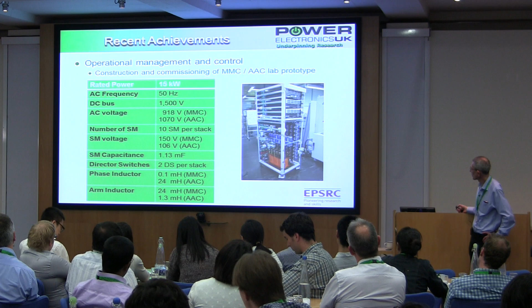What I've got here are a few slides showing the experimental system being assembled at Imperial, to provide a basis for validating some of the techniques Paul was talking about, and also for looking at the fault behavior of these systems. This is a 15 kilowatt system, with 10 switching modules in each stack, and a DC voltage of 1.5 kV.